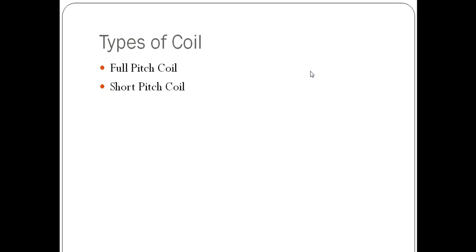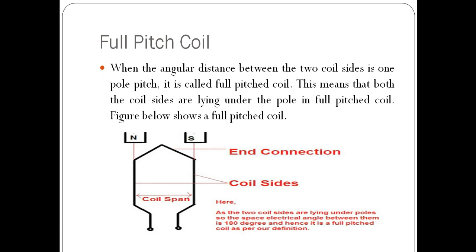There are basically two types of coil: full pitch coil and short pitch coil. A full pitch coil is a type of coil in which the coil span or coil pitch is equal to one pole pitch. As we can see in this figure, both the coil sides are lying under the poles of the machine, so the coil span or coil pitch is equal to 180 degrees — hence this type of coil is known as a full pitch coil.